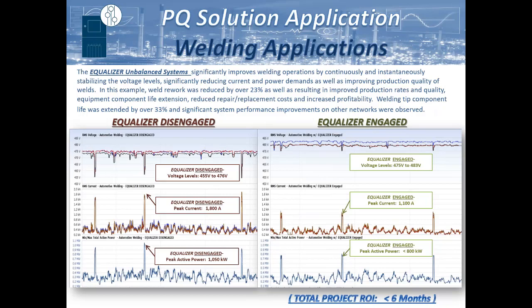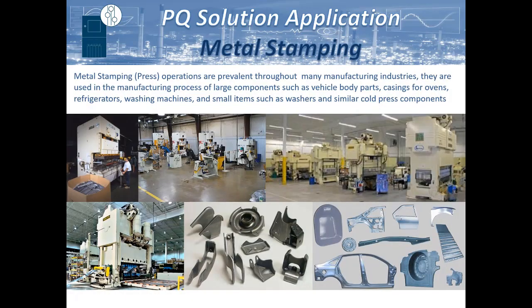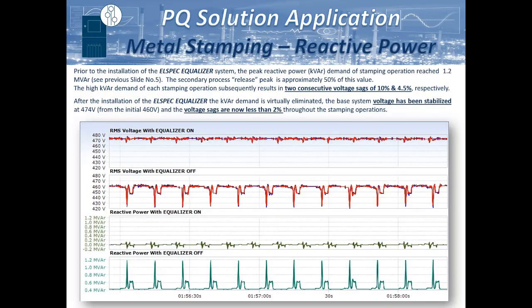So we're basically mitigating all of the impact of the treated area from the rest of the network. Metal stamping is another good application, lumber mills as well. Anything that's very dynamic in nature. You can see here in this one application, they're already running a somewhat low nominal voltage level, about 460 volts.